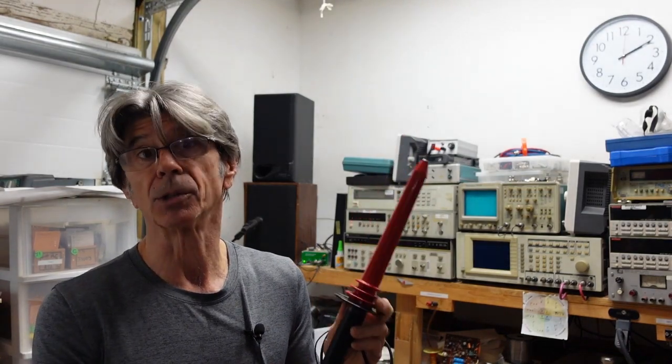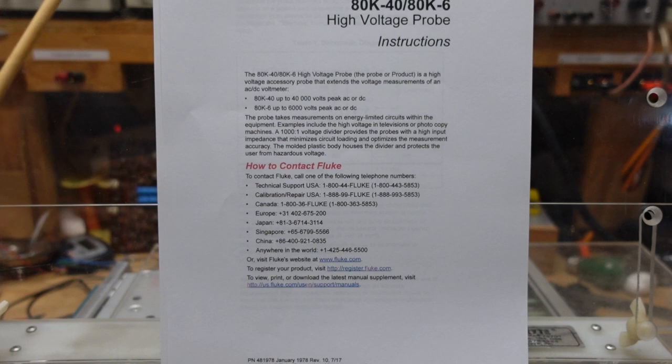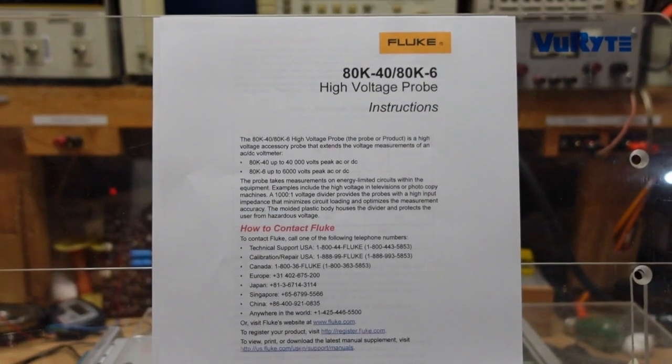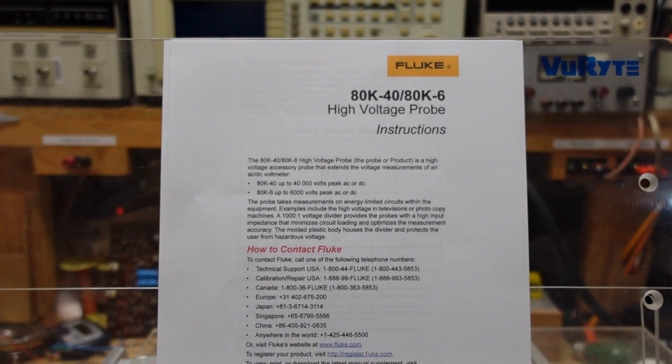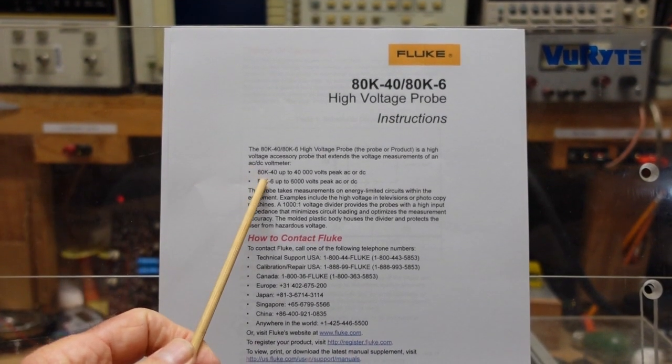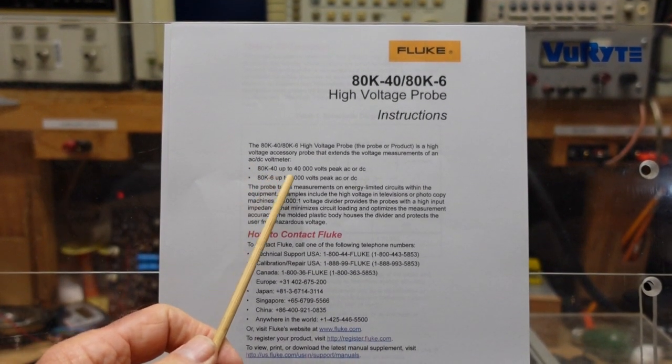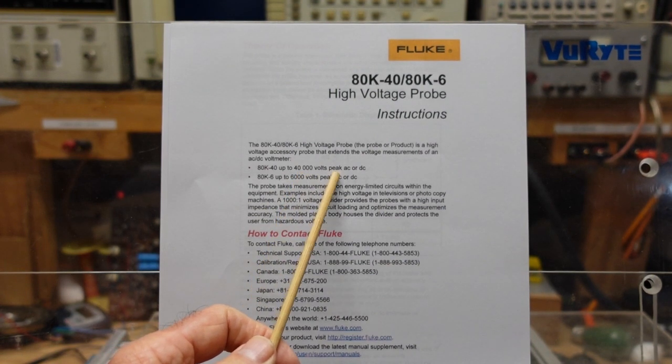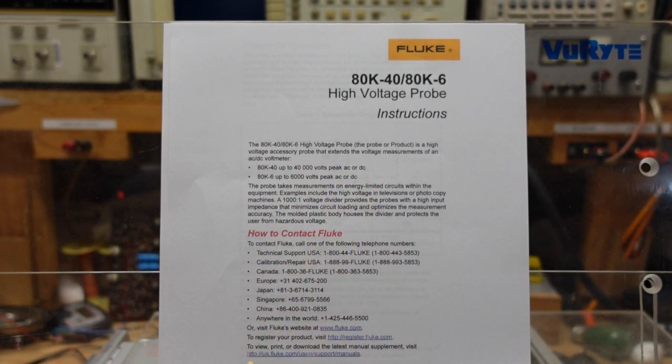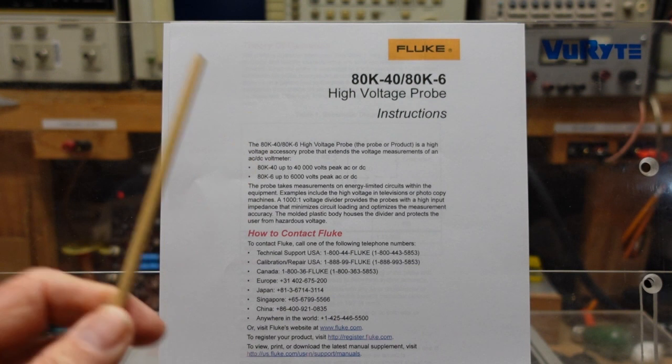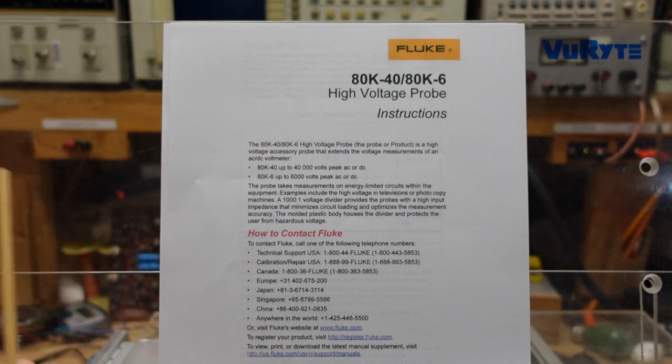Here is the manual for the Fluke 80K, and you can see here it tells us that our 80K-40 is good up to 40,000 volts peak AC or DC.